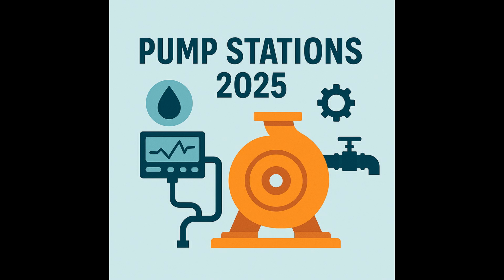This is literally drawing the safe box of operation for the pump. It defines the minimum and maximum limits for everything: flow, head pressure, NPSH, efficiency, even vibration levels. Okay. And within this boundary, you explicitly mark out the preferred operating region, the POR, and the allowable operating region, the AOR. So it's like mapping it all out.